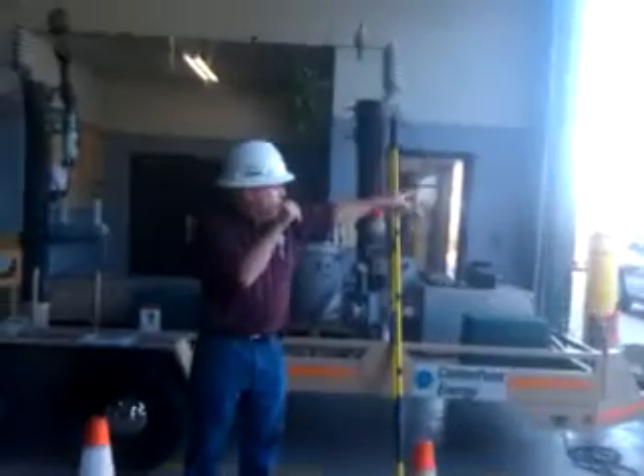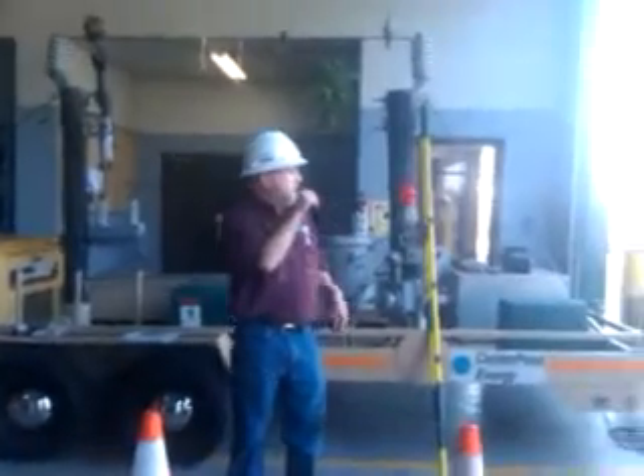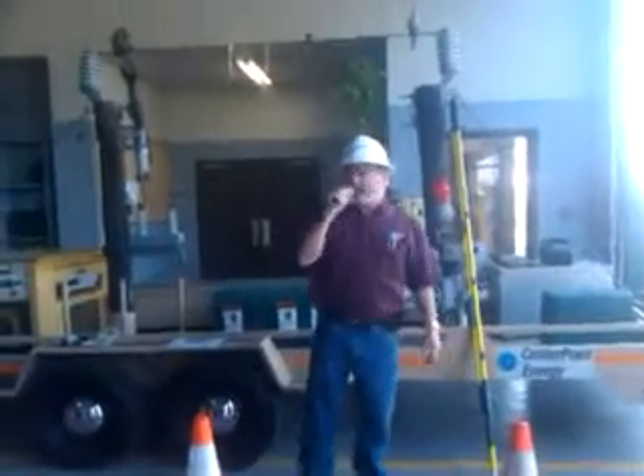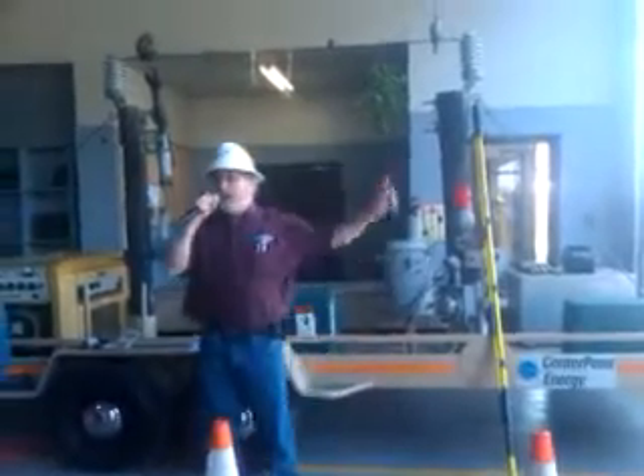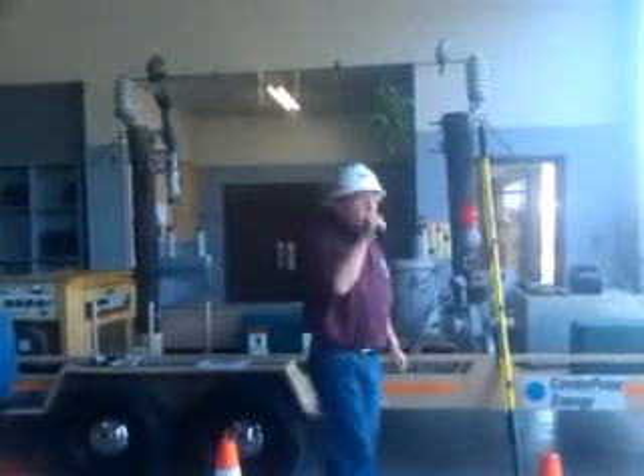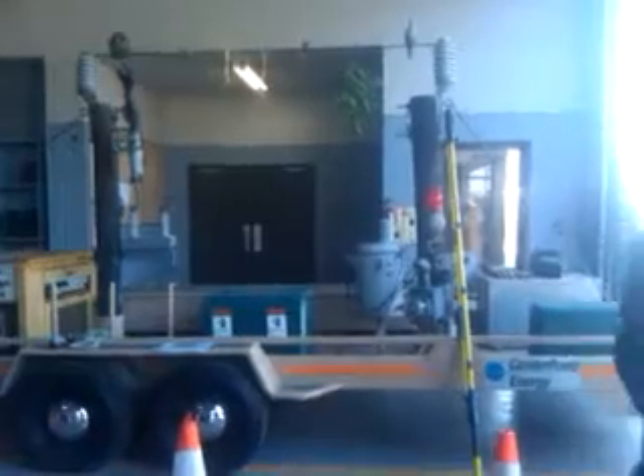Between any two of those 3 phases below, the high voltage is 34,500, and from one wire down to ground, it's 19,920. And out here around the corner, if some of y'all can see it, that's a 138,000 volt transmission tower.